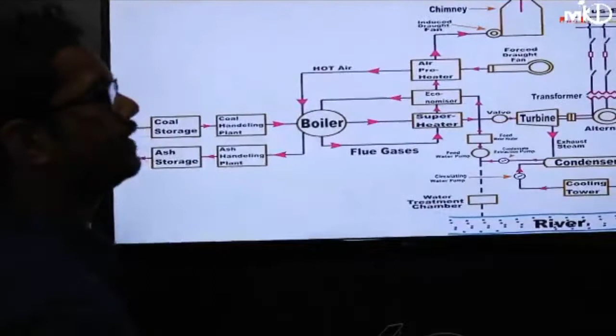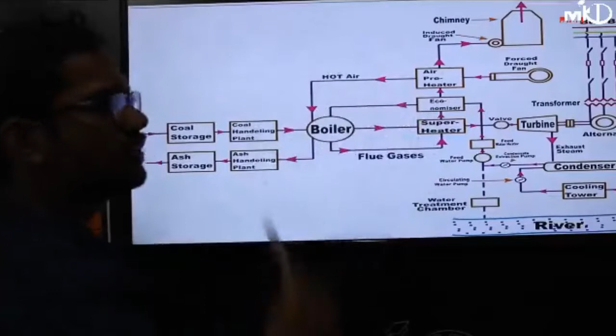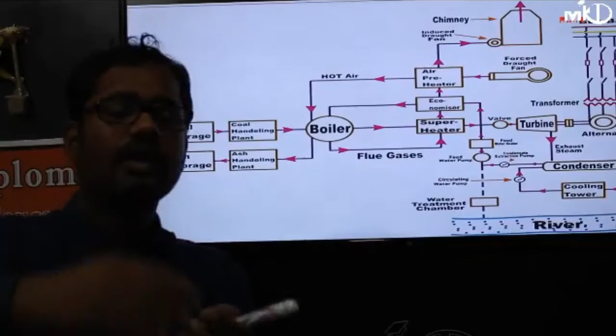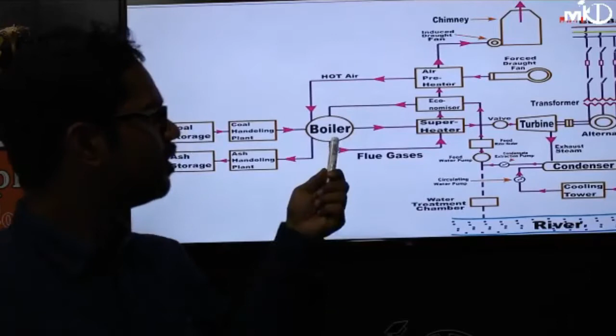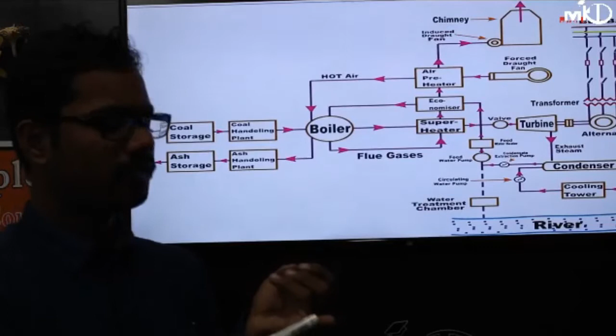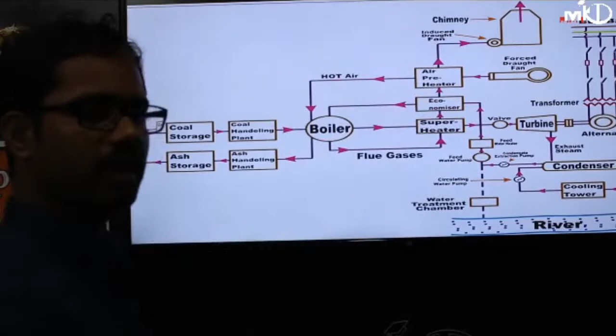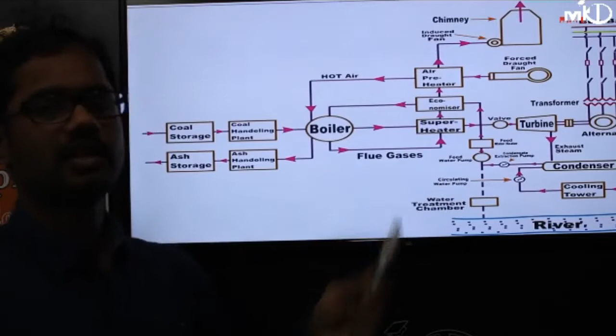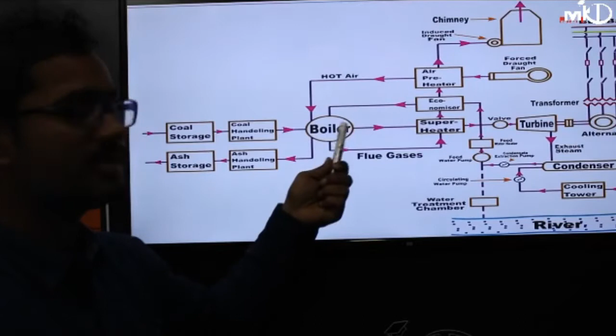Okay. Then comes the economizer. What is the economizer? It is the water inlet to your boiler. In the economizer, we are increasing the temperature of the feed water. In your boiler, the requirement is coal, air for proper burning, and water. If you put cold water inside the boiler, then for producing the required amount of heat, your requirement of coal will be more. So if we increase the temperature of the water to some extent, the efficiency of the boiler increases and the requirement of coal will also reduce.